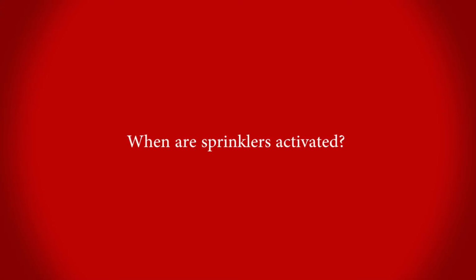Sprinklers are only activated by heat. Each sprinkler head is heat rated. Most of your heads in your business occupancies are about 165 degrees. Now, we've talked many times about the misnomers of sprinkler systems. When one sprinkler head goes off, it's only the head that's affected by the heat source that goes off. They don't all go off. Typically in your James Bond movies or your Jack in the Box commercials, you'll see somebody pull a pull station and a whole sprinkler system goes off. Well, that's not how they're designed to work.